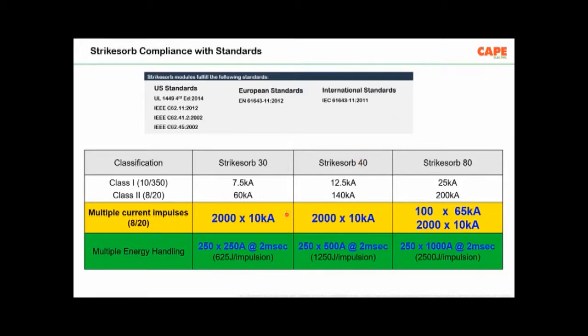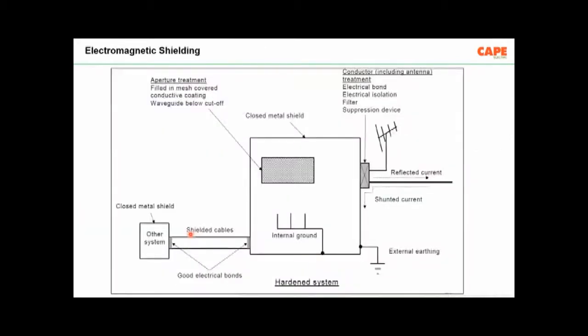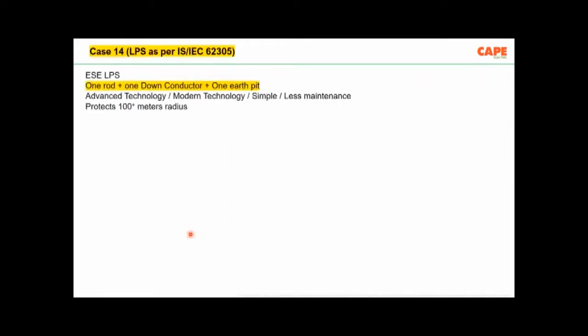These bus bar mounted SPDs are tested for multiple strikes. Say, for example, 2000 strikes of 10 kiloampere, and 100 strikes of 65 kiloampere. So for critical electrical installations, you need these kinds of high quality SPDs. As for the shielding, now I skip this part.